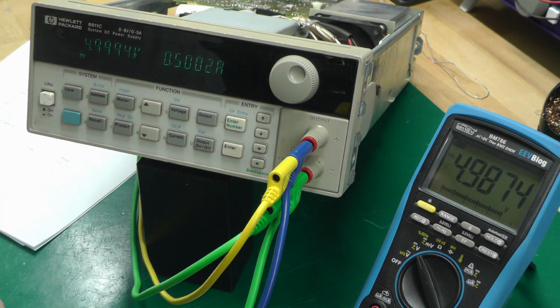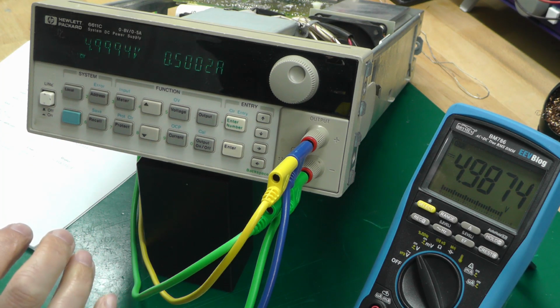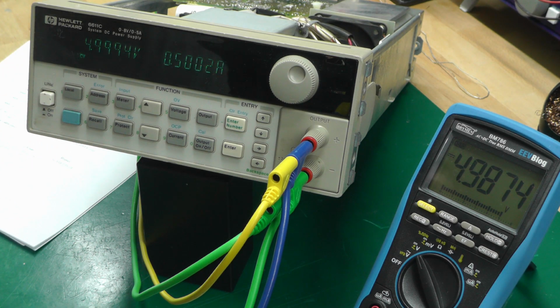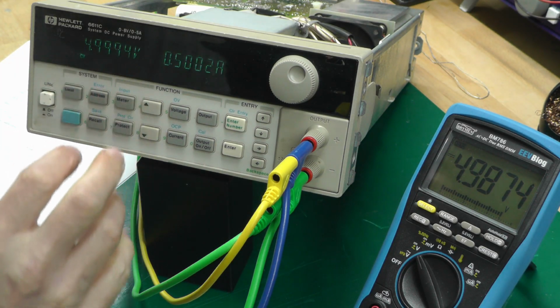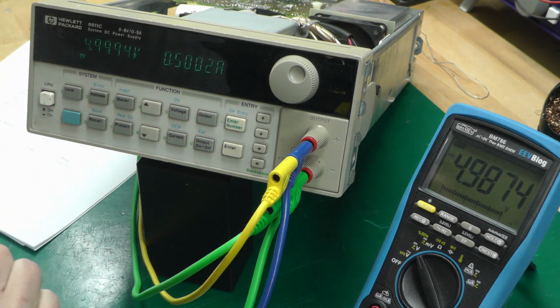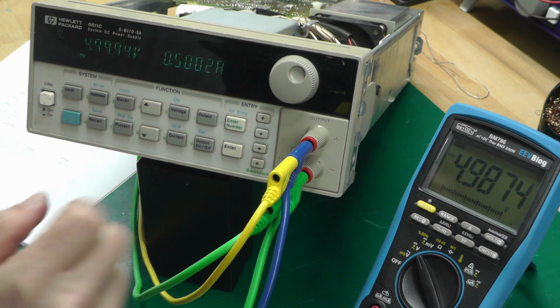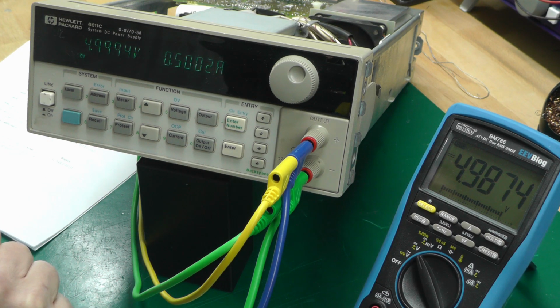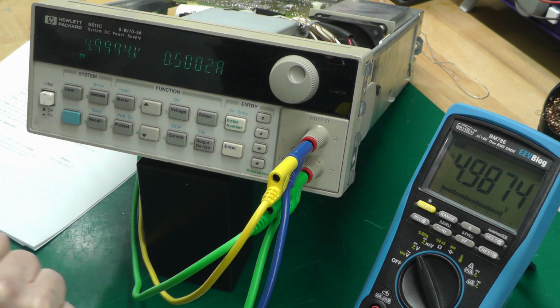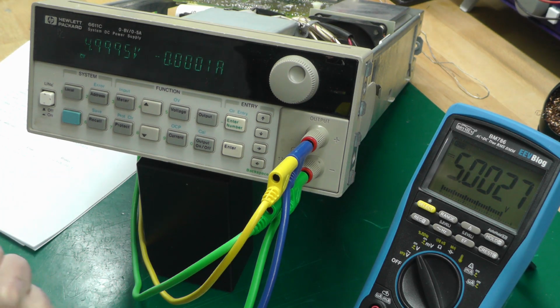Why would the calibration be lost? Well, it could have been that the flat flex got broken, whatever, and somebody powered it up, noticed the power supply wasn't working, and maybe made some attempt to recalibrate it. Who knows, and it saved it, you know, but it wasn't that far out. It was only a little bit out. It wasn't like it was miles out or completely upset totally. So I'm not too sure about that. Turn the electronic load off. But anyway, it seems to have recalibrated, so it seems to be working.